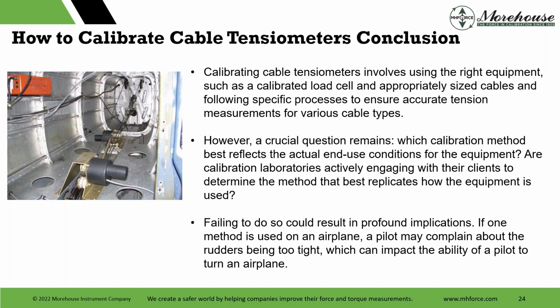The Navy does it the one way, they clamp and then adjust. Air Force uses dead weight for some, uses other systems for others. What is the best method here, and what actually replicates use, and replicating use versus standardizing across dead weight? Or are we just to say, since on dead weight you cannot just clamp, because you do not have 2 fixed points, it does not replicate end use, and should dead weight just be thrown out altogether? That's another thought process that you could have, because it doesn't simulate what's going on here with 2 cables that are fixed.